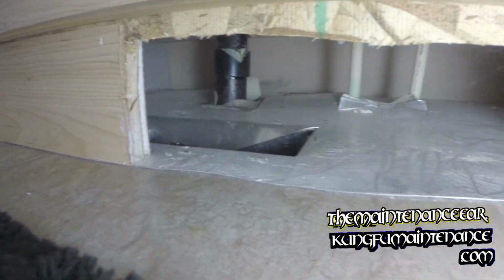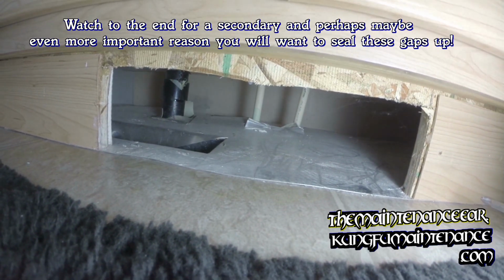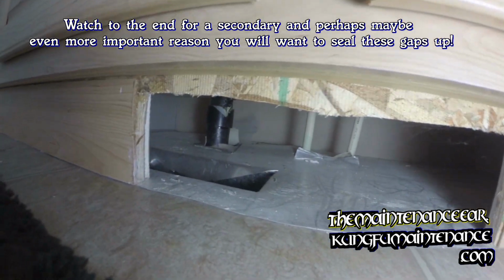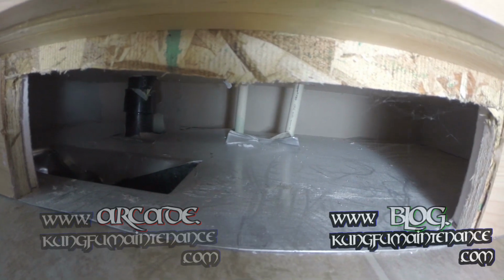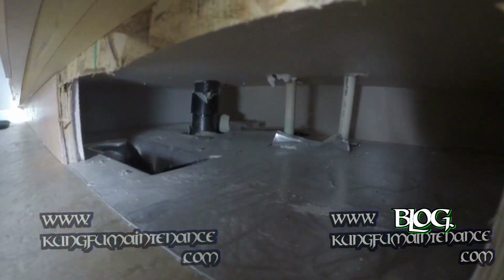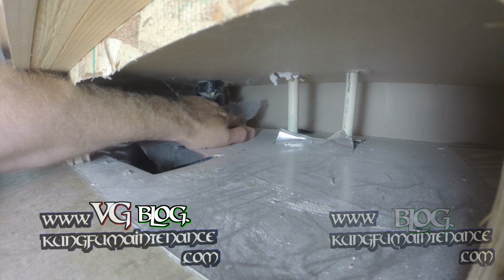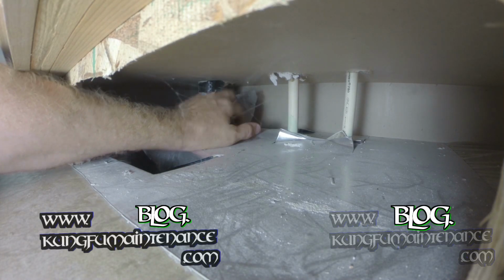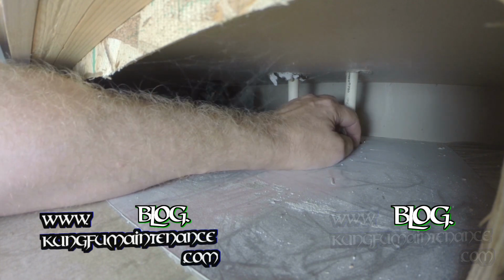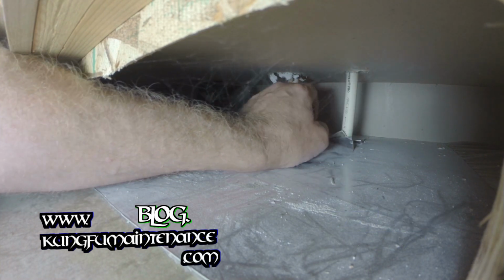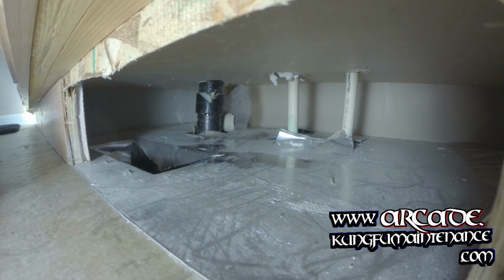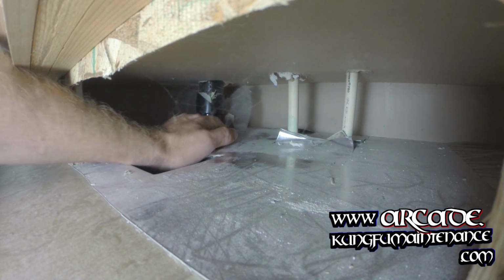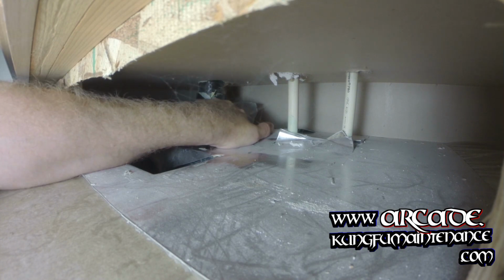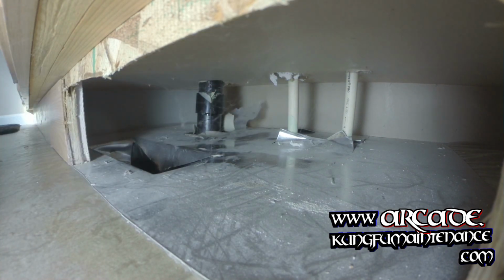Okay, here's the ductwork where it comes out. They're basically just using the cabinet to deliver the ductwork. But if you look further back there, around all the plumbing, you can see flapping in the wind. You're going to see openings. See, I can reach my finger down in right here, and I can reach my fingers down in right here. All of these openings where the plumbing came through, and the plumbing's been passed through, they're not sealed, they're open, and they go right down under into the crawl space.